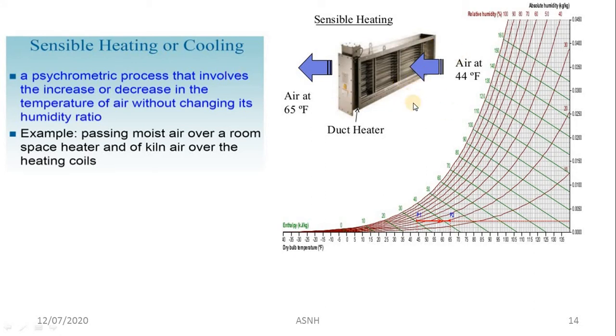For sensible heating, consider a duct heater with heating coils. Air passes through the heating coil to increase its temperature — for example, from 44°F to 65°F. The psychrometric process involves an increase or decrease in air temperature without changing the specific humidity ratio.